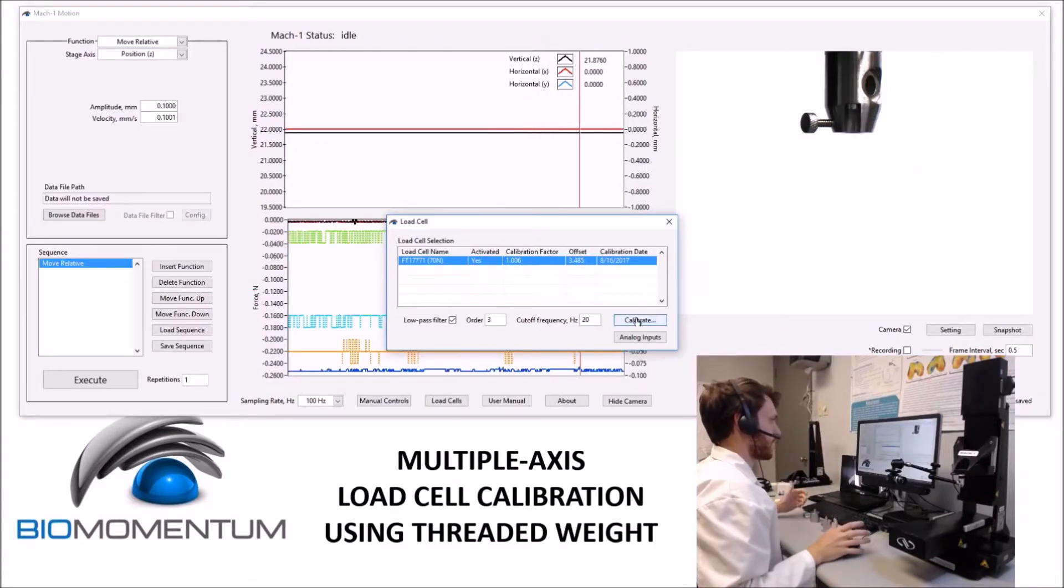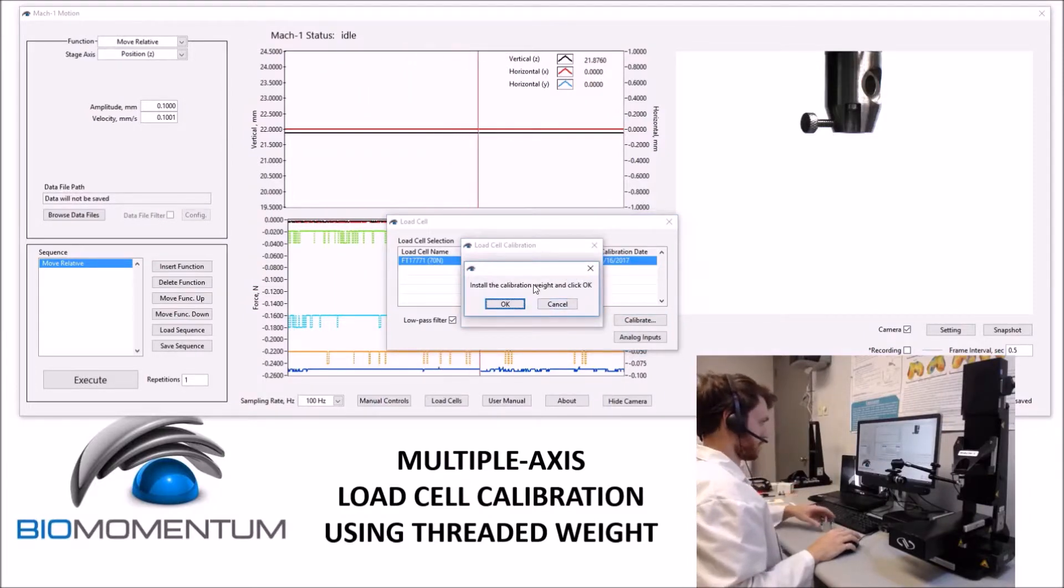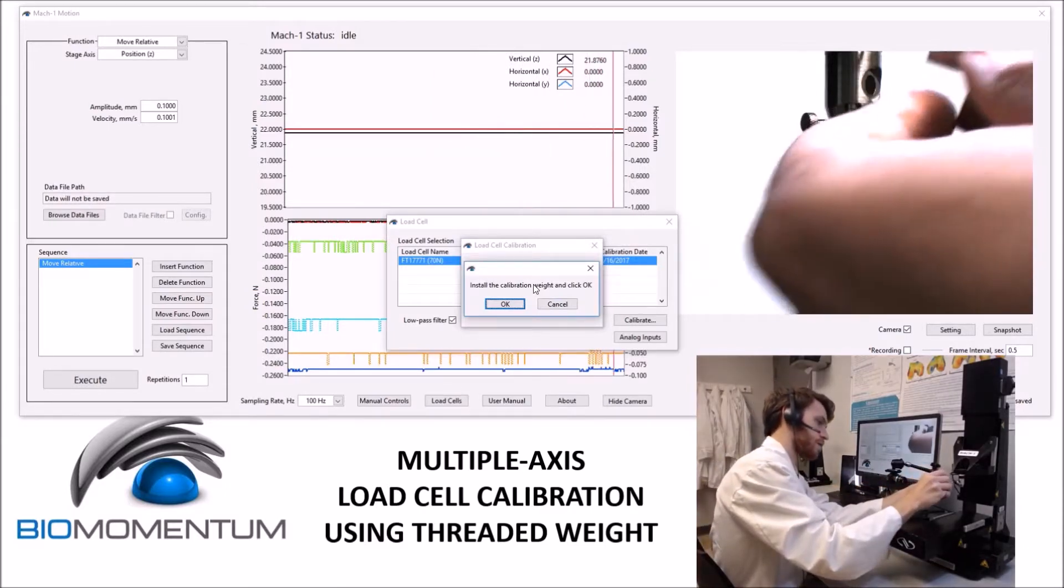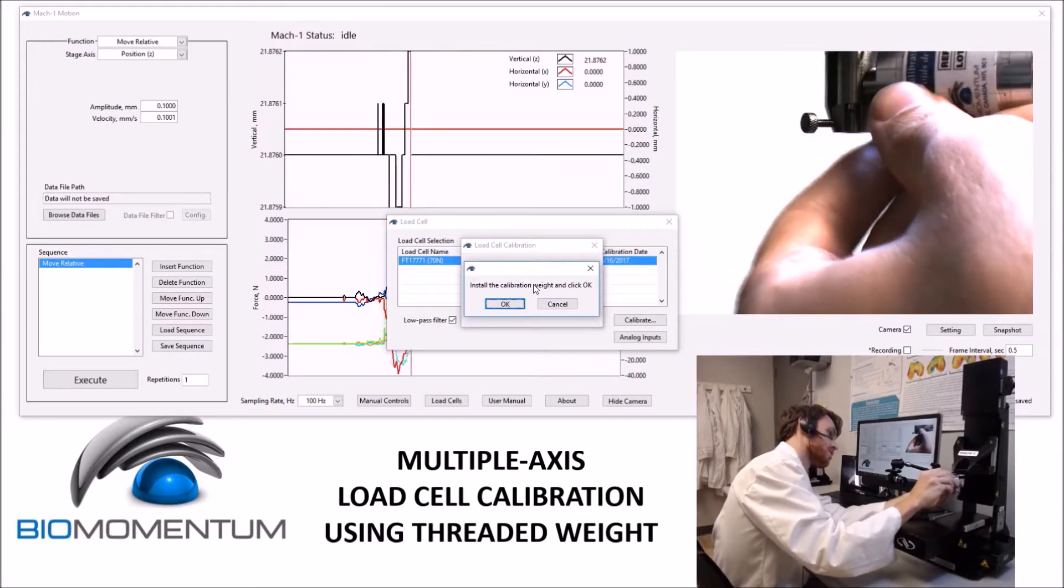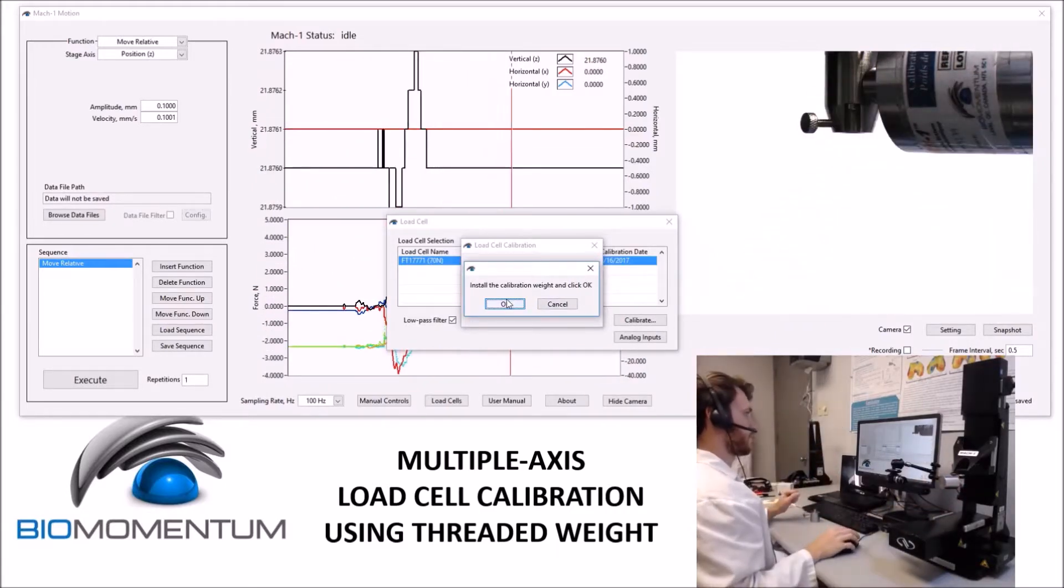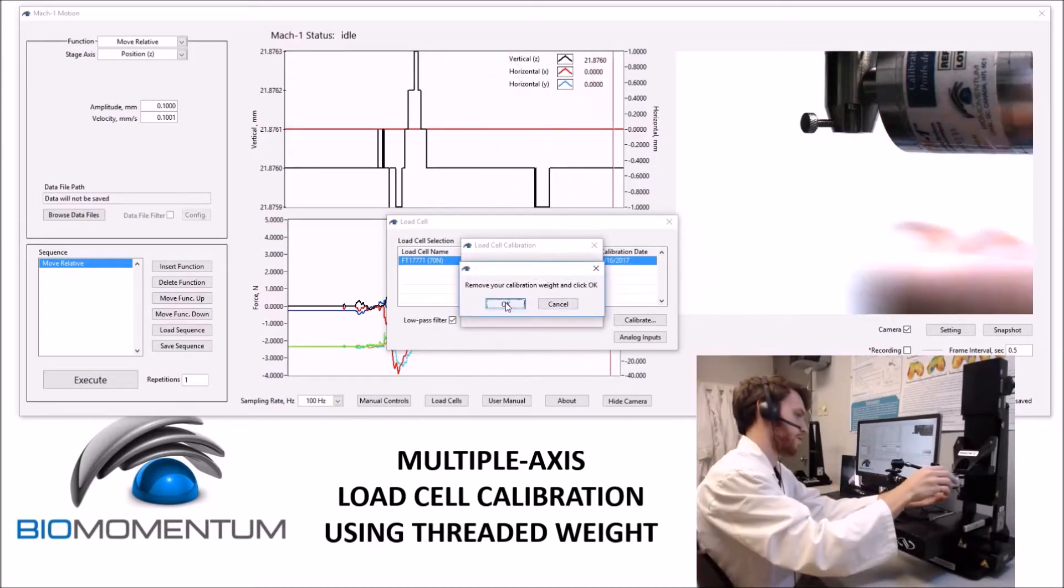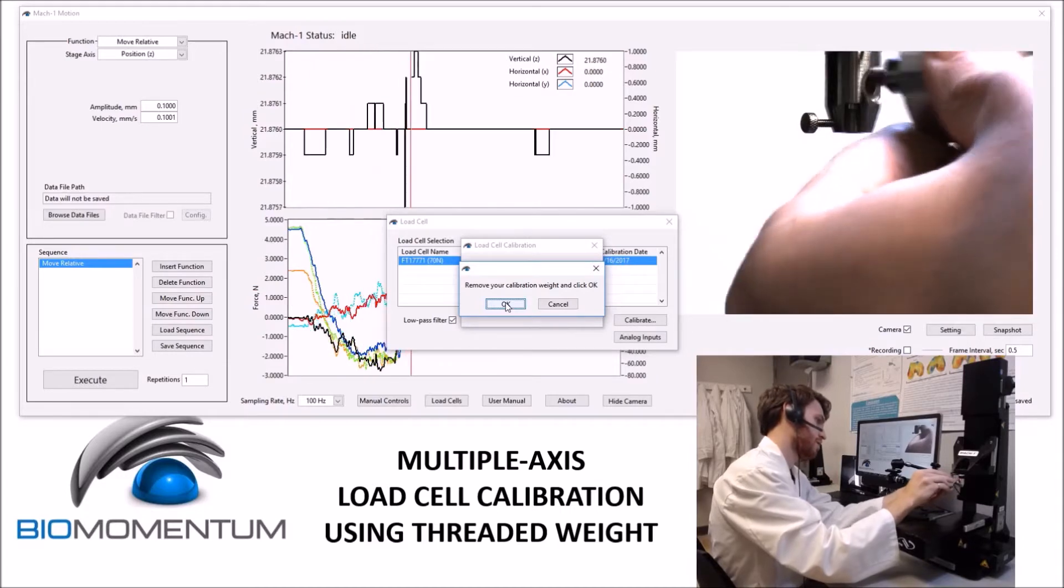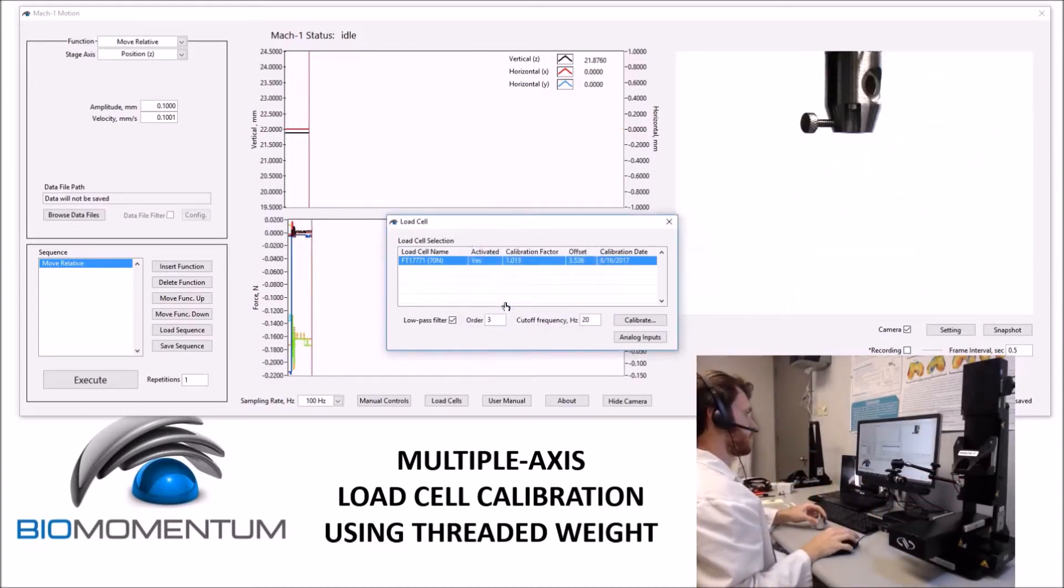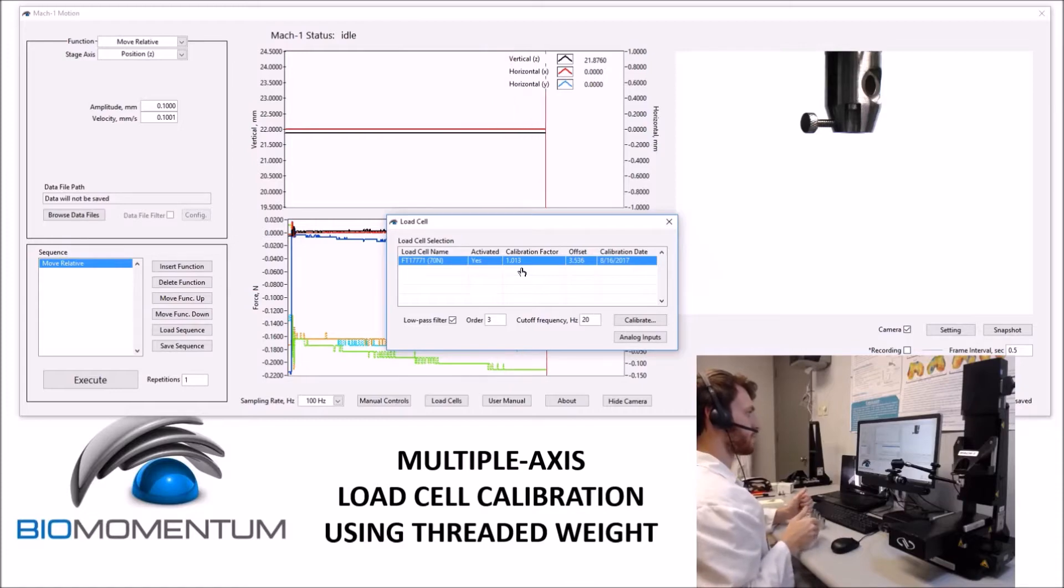The second method to calibrating the multi-axis load cell is to select Calibrate, and select a threaded weight, and follow the instructions on screen. The calibration weight will be placed into the side insert on the multi-axial load cell. The instructions will be followed on screen, being careful not to damage this load cell. And the calibration factor will again be within 5% of 1.00, from 0.95 to 1.05.